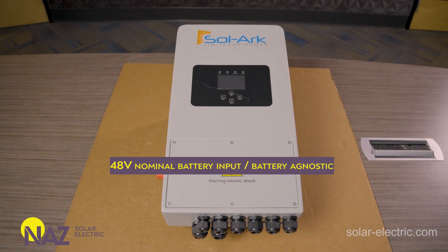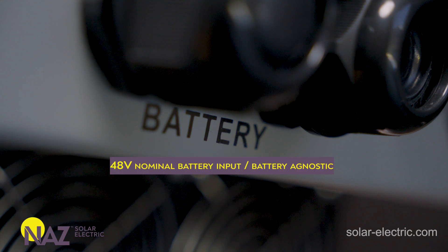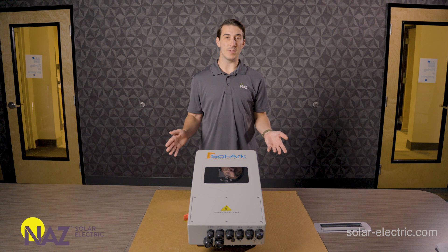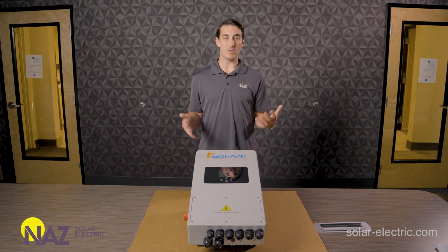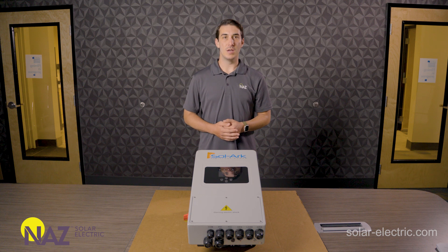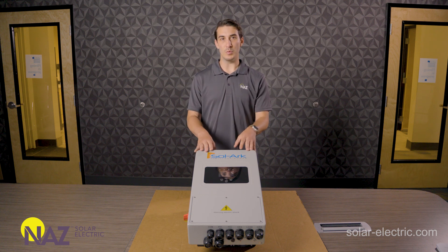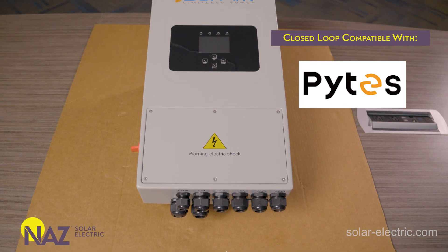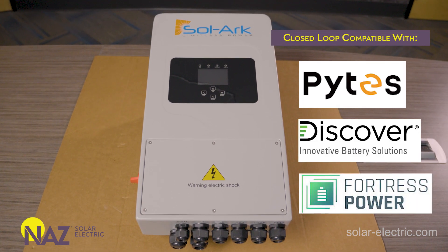This model, just like the rest of the Sol-Ark family, has a 48-volt nominal DC battery input. It is battery agnostic and works with virtually any 48-volt nominal battery. Regardless of chemistry, you can custom program the unit to match. It does offer closed-loop communications with several lithium battery manufacturers like Pytes, Discover, and Fortress.